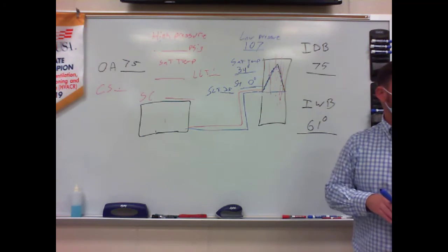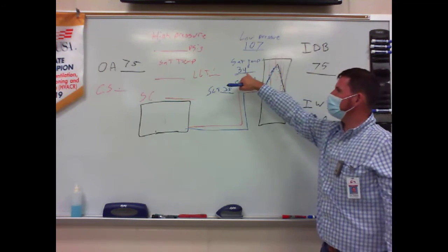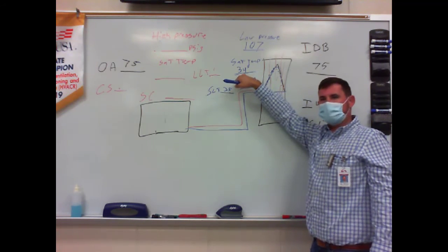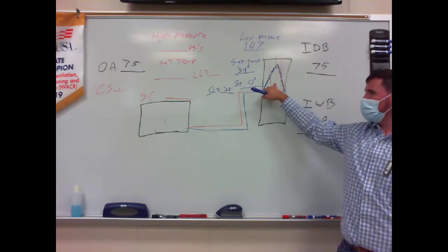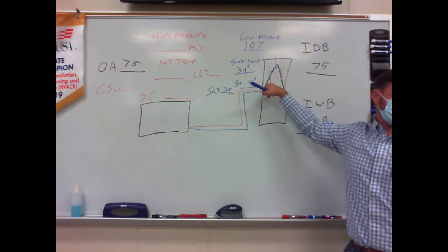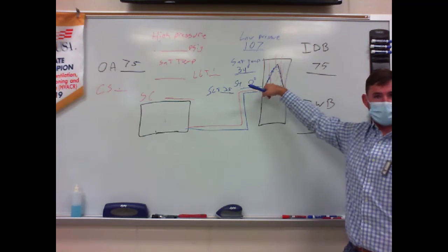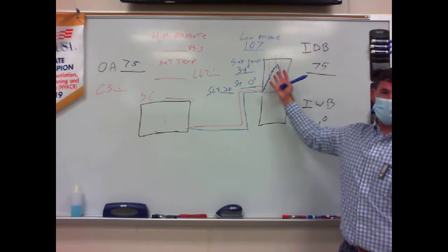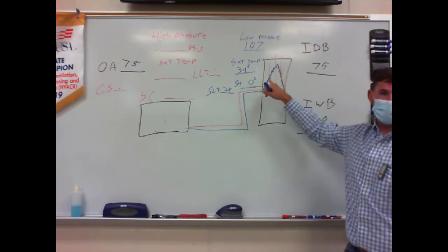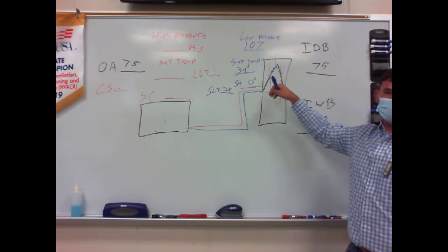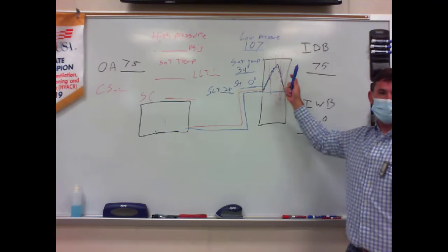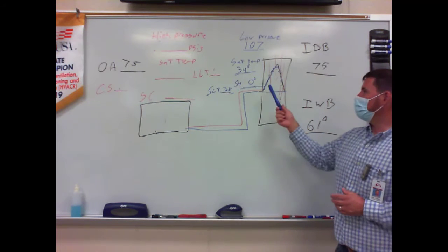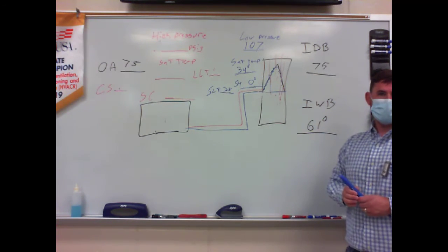But the other thing I've got to look at now, if I start removing refrigerant, my temperature is going to drop. So maybe it's not a refrigerant issue alone. Maybe that thing has a dirty coil in it and it's not picking up heat. Or maybe my airflow's bad. I don't have enough air going across it. If I don't have enough heat hitting that, I'm not going to be able to evaporate what refrigerant I have in there. I mean, it could be. It was still blowing good. I'd have to check airflow to see if it's blowing as good as it should be. But if I had a suggestion, it would be probably to clean that coil. It's probably dirty.